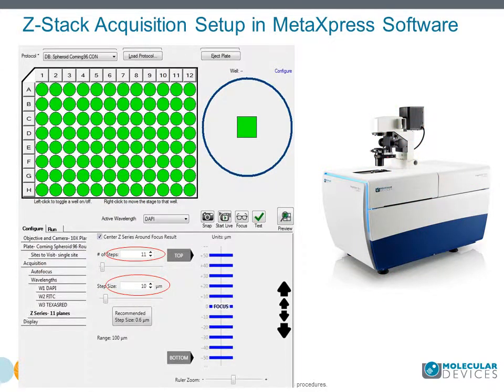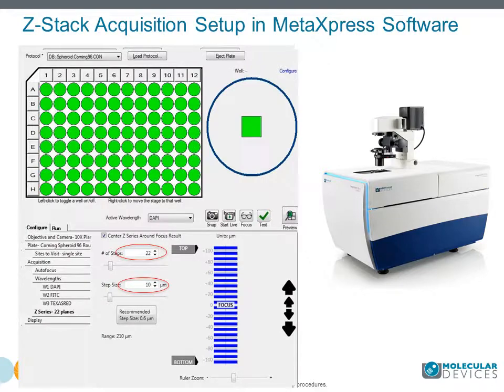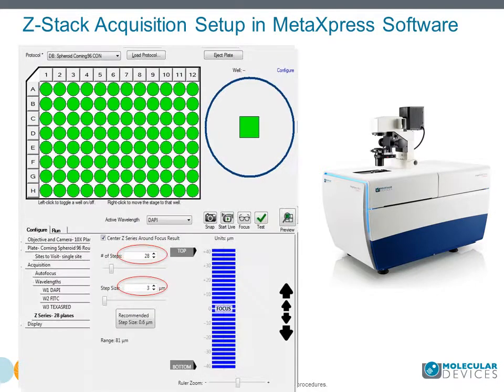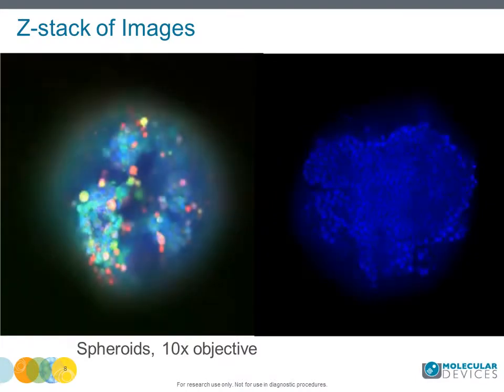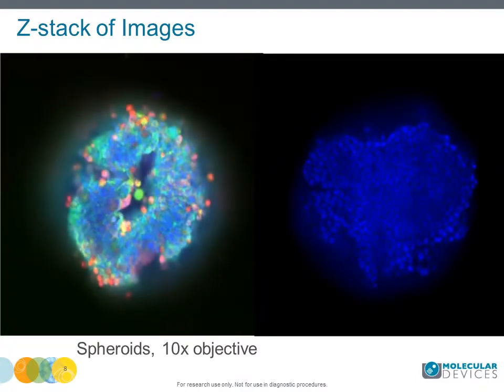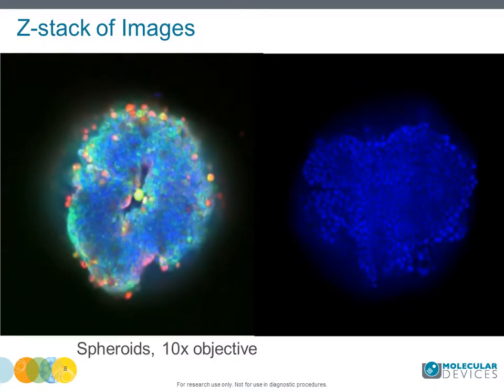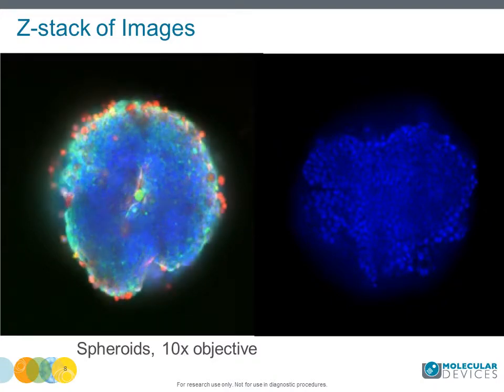Images should be taken using automated confocal mode with a large field-of-view camera. MetaXpress software allows modification of the number of z-planes and distance between planes. Using a 10x objective, you can capture 10–15 images with 10 micron distance, or more than 20 images with 5 micron distance.